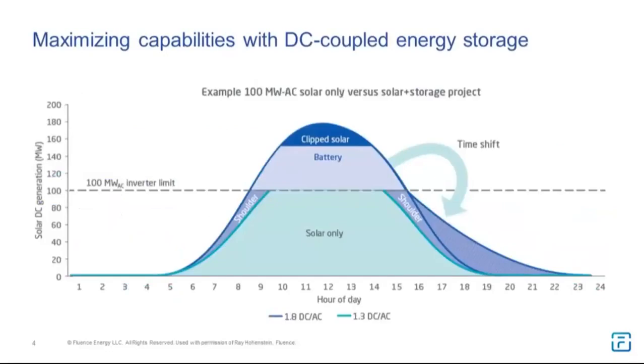The reason you really love to do DC coupling is you can put a lot of additional PV capacity and battery capacity behind that interconnection, sharing the inverters. If I'm building a standalone PV plant, since panels are cheap, I might already oversize to have 130 megawatts of PV panels for a 100 megawatt solar plant. But if I've got a battery there, I'm probably going to put in 180, 200 megawatts of PV panels, knowing I'm going to clip a lot of that during the afternoon, but I can charge the battery with that and use that battery capability for other services. Not just energy, but ancillary services, reserves, you name it — you can do everything. So the whole idea of a hybrid is you're going to have a lot of additional capacity back there that's used for delivering a whole range of very flexible services to the system.